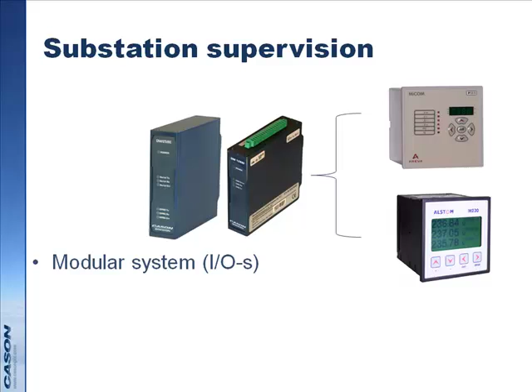It is a modular system with different I/Os. We use the same GPRS communication, but it's also possible to use Ethernet or fiber optic based communication and use GPRS as a fallback, or vice versa. In many cases GPRS is much more cost effective than others. We provide a multi-vendor solution, meaning in many cases we connect to ABB, Siemens, or Areva equipment. Areva has a very strong footprint in the Middle East, and Siemens here in the UAE, as far as I know they are the most preferred vendors for substation equipment.